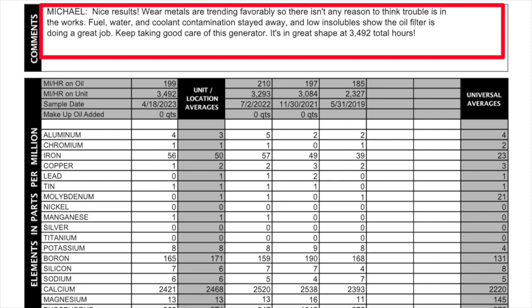On this last report, iron went down to 56 — actually dropping one from the previous. Their comments were: 'Michael, nice results. Wear metals are trending favorably, so there isn't any reason to think trouble is in the works. Fuel, water, and coolant contamination stayed away, and low insolubles showed the oil filter is doing a great job. Keep taking great care of this generator — it's in great shape at 3,492 total hours.' That final comment made me feel very, very comfortable about the iron levels. I knew I was running the generator differently over that period, so I expected something, but having Blackstone and their expertise analyze this is really a great thing.